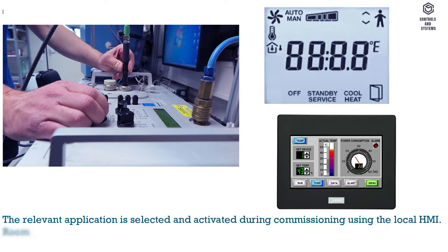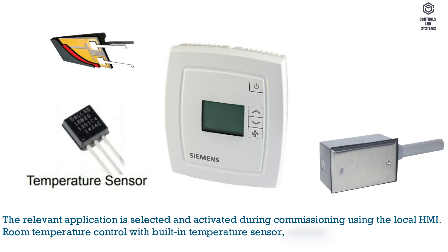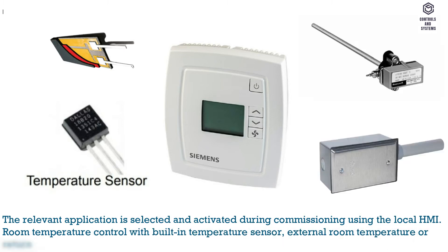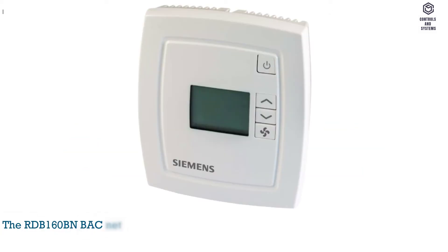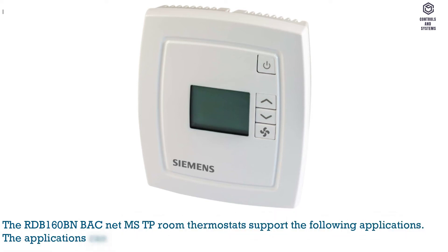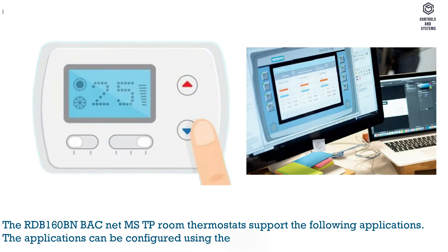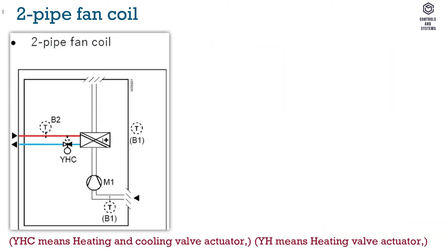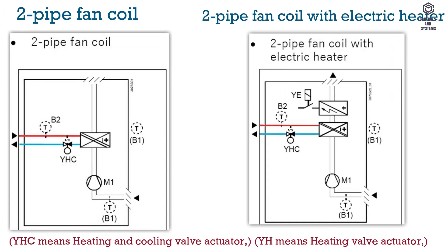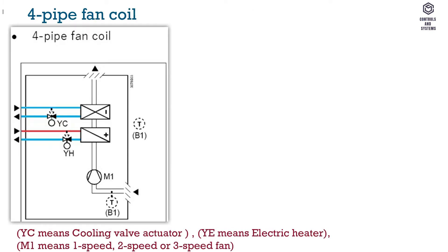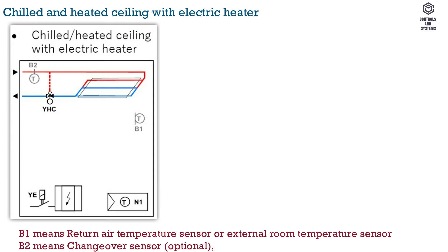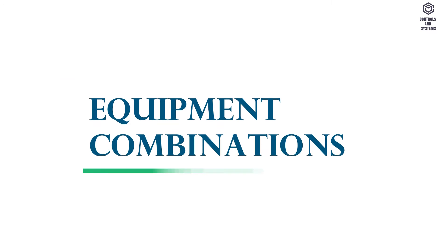Using the local HMI, room temperature control is provided with a built-in temperature sensor, external room temperature, or return air temperature sensor applications. The RDB 160BN BACnet MS/TP room thermostats support the following applications, which can be configured using local parameter settings or via the system: two-pipe fan coil, two-pipe fan coil with electric heater, four-pipe fan coil, chilled and heated ceiling, chilled and heated ceiling with electric heater, and chilled ceiling with radiator.